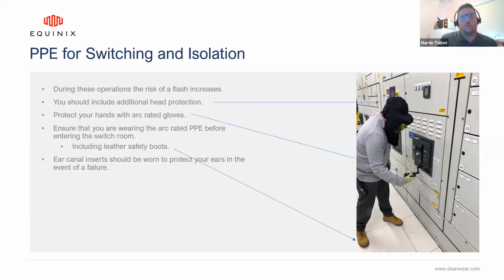Okay, so when we're carrying out switching, we want to be wearing the correct PPE. During these times, the risk of arc flash increases because the risk of human error increases. We might have just carried out maintenance. There could be a problem, tools, whatever. All these things that we should avoid, but sometimes they don't. So that's why we increase our protection. We wear head protection for switching, gloves for carrying out switching if we have to do it in front of the switchgear, and we're always wearing the correct rated arc flash PPE.